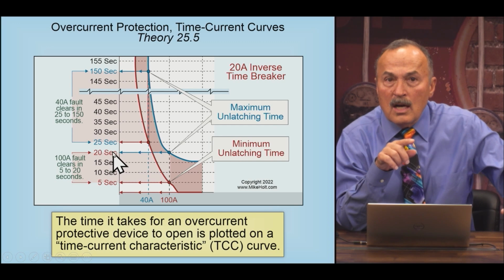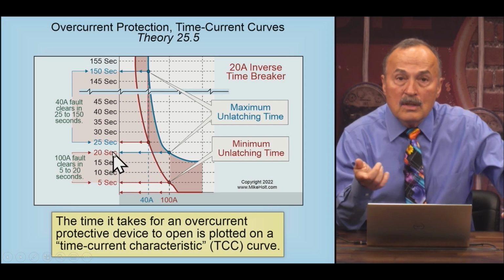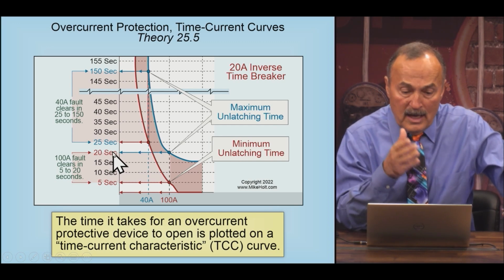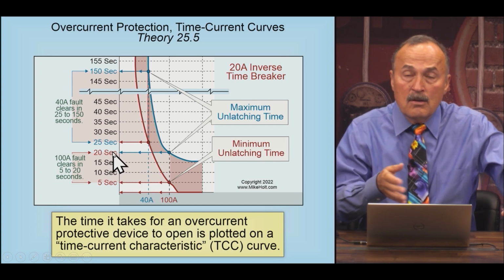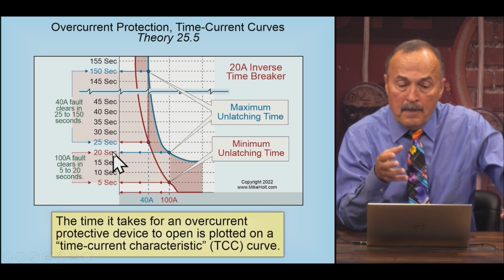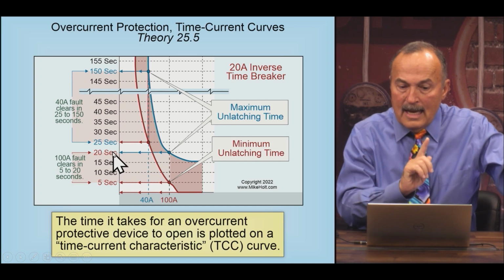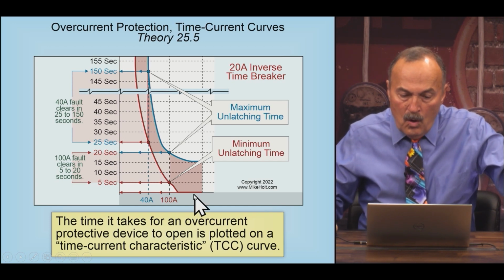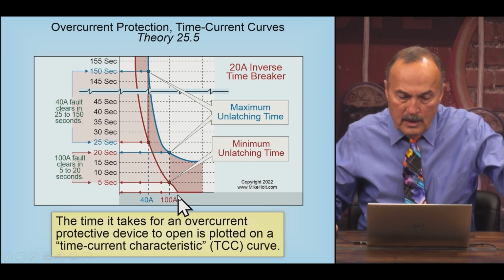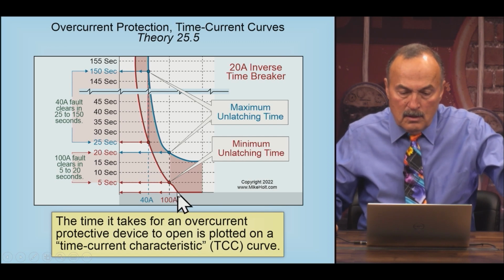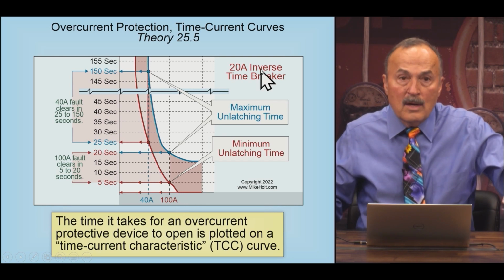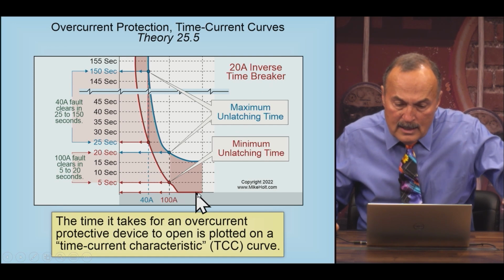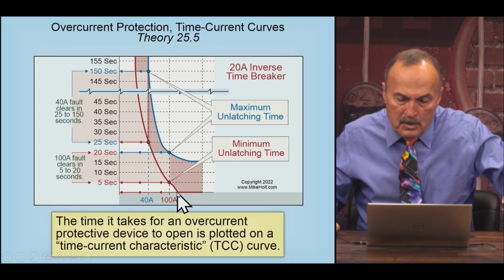And this one we were talking about the inverse time characteristics. This applies to fuses. If we had a time current curve, we could have done the same thing here and shown this as a fuse. Now, what's the next step? If you go all the way over here to the right, and let's assume that this number is significantly greater, so maybe 500 amps, right? Well, if you put 500 amps on a 20 amp breaker, this line right down here, which is not quite perfect, but this line down here is that it's going to trip.